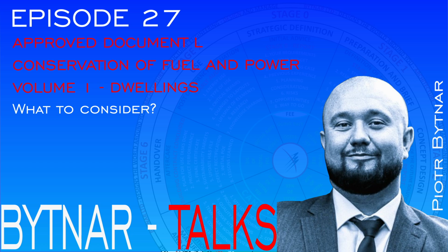Section 8 mandates the commissioning of fixed building services and on-site electricity generation systems to ensure proper operation and compliance with regulations. A commissioning plan detailing the test procedure must be submitted to building control, with a notice confirming completion required within up to 30 days. Specific systems like hot water, heat pumps, community heating and underfloor heating must adhere to these designated standards and procedures, including system cleaning, flushing and appropriate chemical treatments.